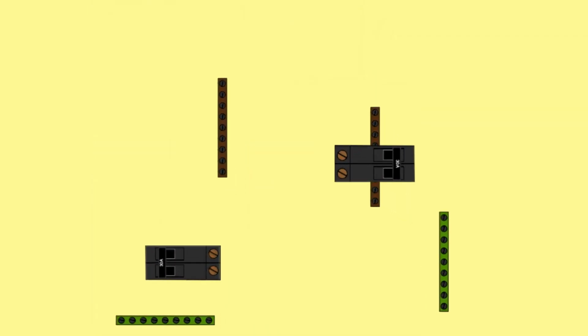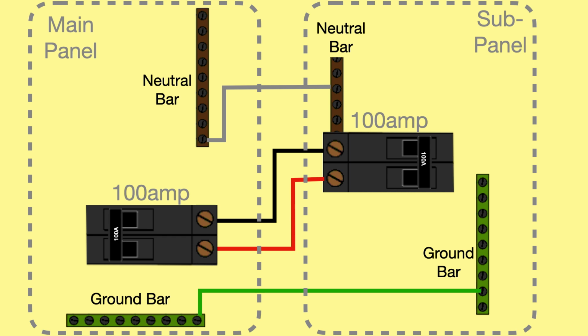In actual fact, the connection is fairly simple. A 100 amp double pole single throw breaker in the main panel is connected in parallel to a 100 amp double pole single throw breaker in the subpanel. This connection energizes the two bus bars in the subpanel. There is a connection between the neutral bars of the two panels and a connection between the two ground bars of the two panels. The wire gauges are the same as those specified for 100 amps.